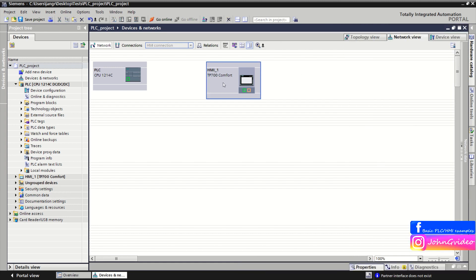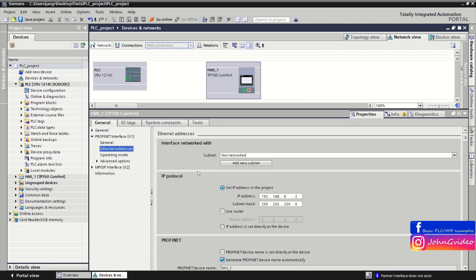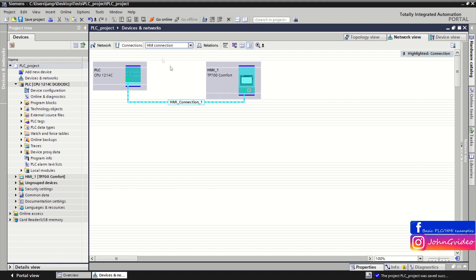Same as with the CPU, go to the properties of the HMI and set the IP address of this device. Save the project. Now to create a connection between the PLC CPU and the HMI device, click the connection button in the 'Devices and Networks' window, then click on the Ethernet port of the CPU and drag it to the Ethernet port of the HMI. Now you have a connection between the two devices.